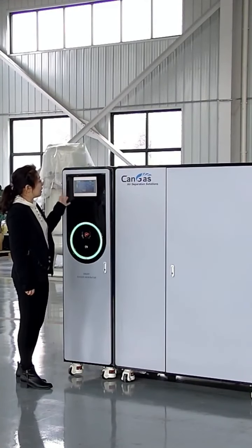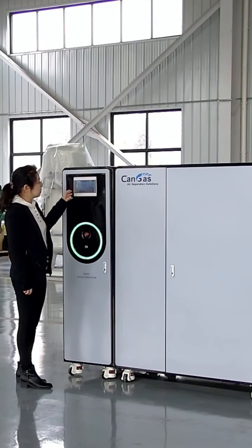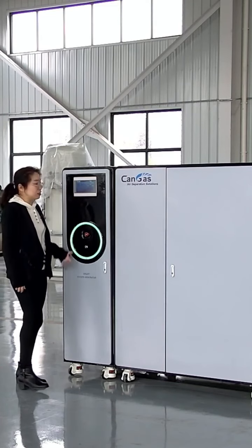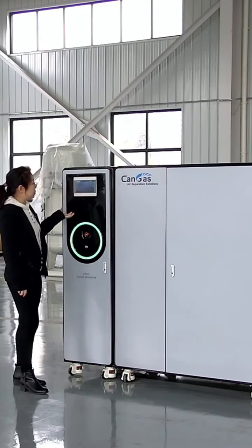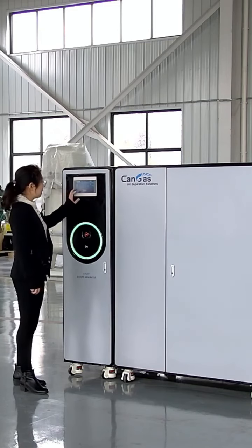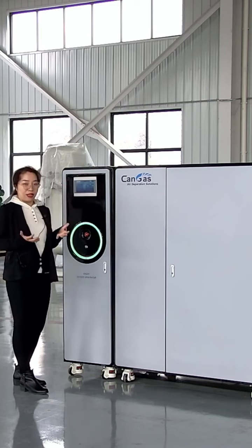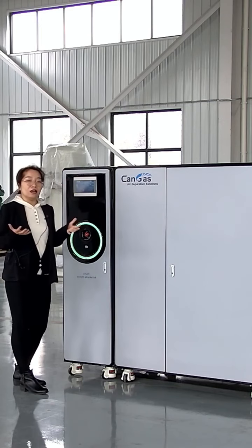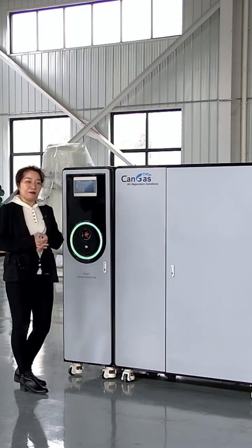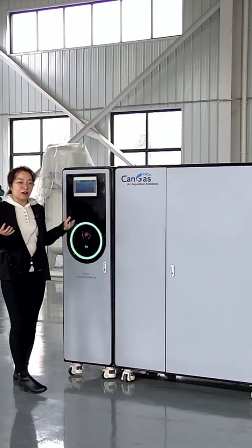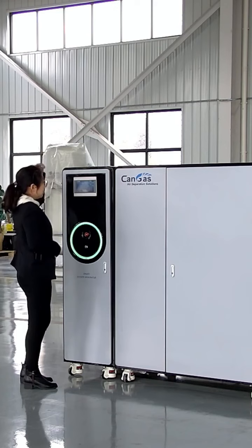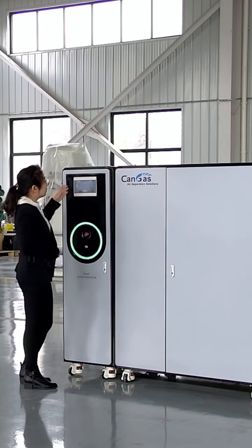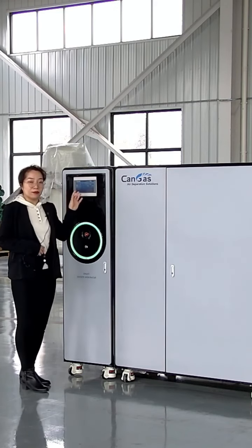has automatic control software, like I have introduced in our video. It has a maintenance time alarm, how long it has been running, and how much nitrogen it has accumulated in production. You can see this is a different level segment.